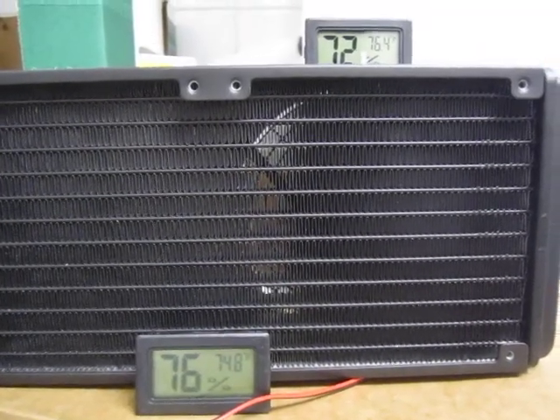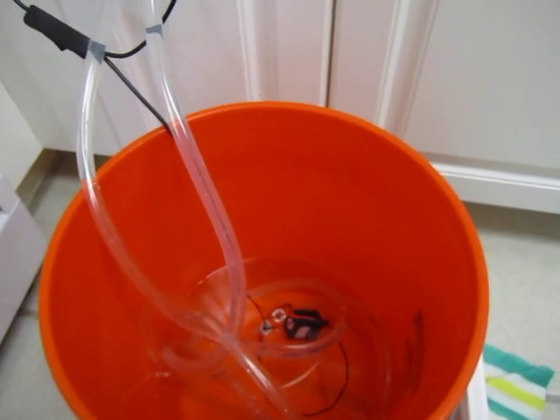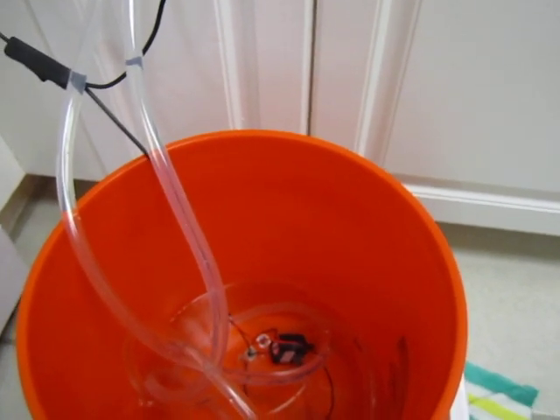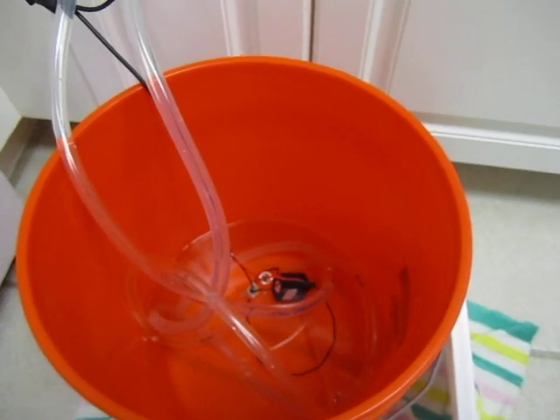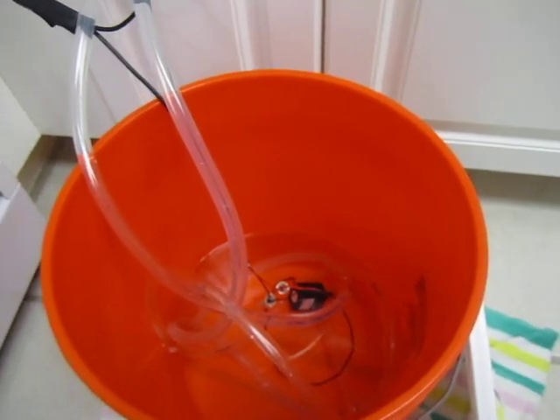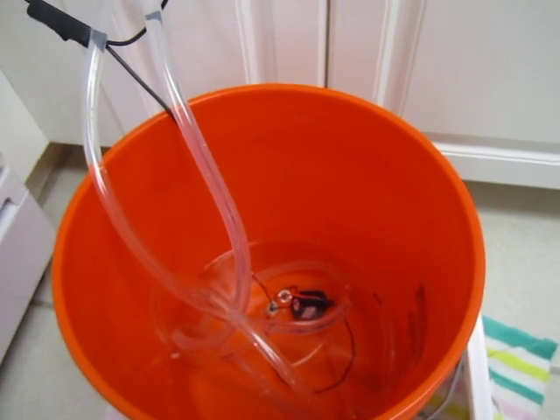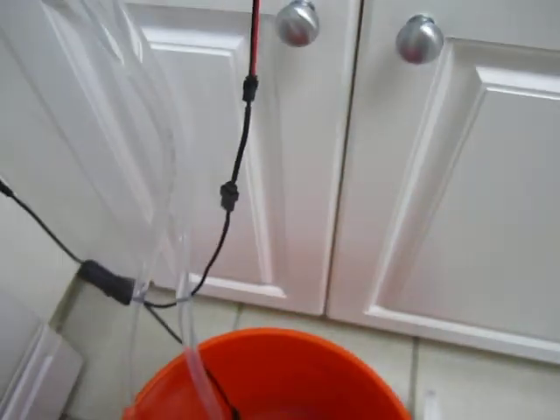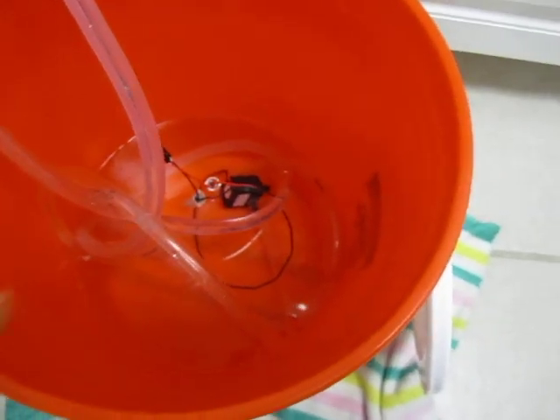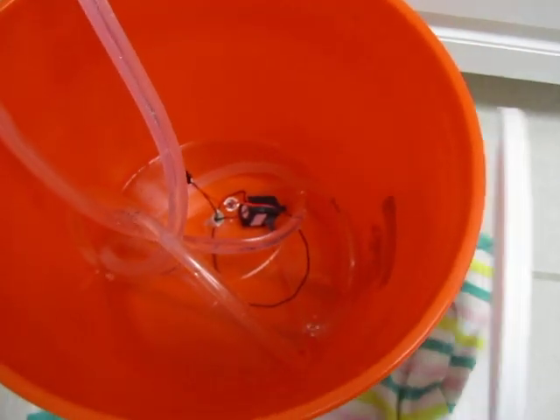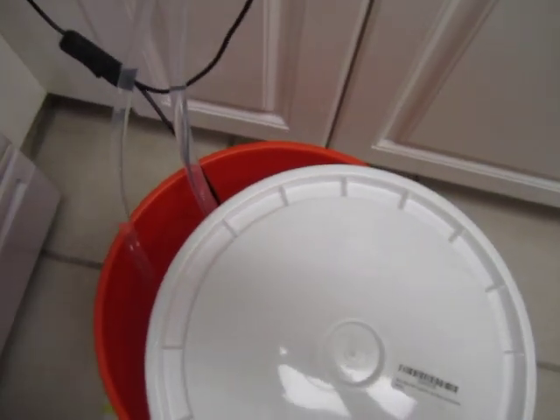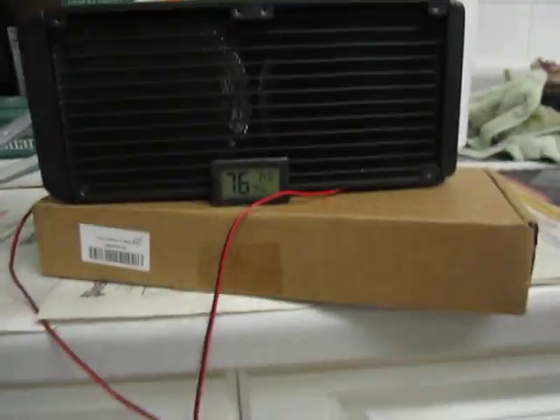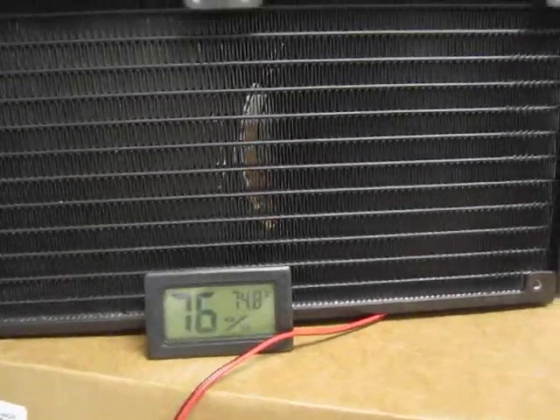Now, the important thing I want to mention here is this solution does not add humidity to the air. It's not like an evaporative cooler, which doesn't work in humid places in the summertime because it increases the humidity when what you really want to do is decrease it. This is not releasing water into the air. In fact, we can put the lid on this bucket to the extent we're able, because this is a closed loop system: the water gets piped through the heat exchanger and then goes back into the bucket.